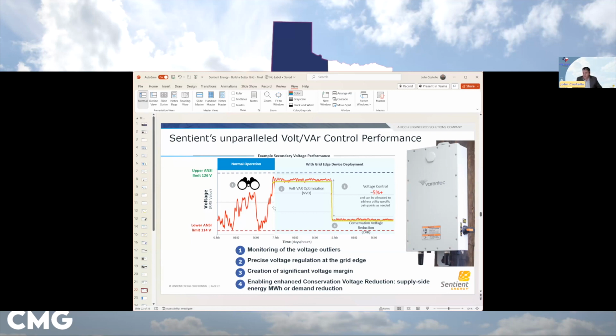LTCs have been in existence for a long time. People have used LTCs to basically drop voltage, but if you're able to control on the secondary side, you can drop it even further. What we've seen is that about 50% of a VVO CVR program's savings are seen by controlling the secondary side. We have a number of clients implementing this now.